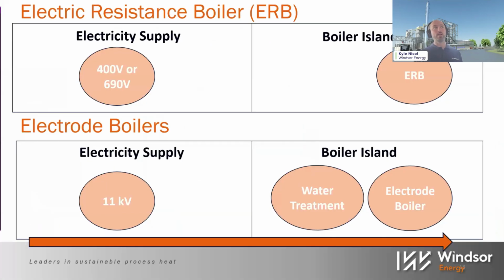And then on to electric boilers. There's two types, which differ in their scale, the voltage, and the water treatment requirements. So you've got electric resistive element boilers, and then you've got electrode boilers. Compared to fossil-fired boilers, all of the electric boilers have a small footprint. They've got a high efficiency, low maintenance, high availability, faster ramp rates, and a very high turn down to say 4% of maximum continuous rating.